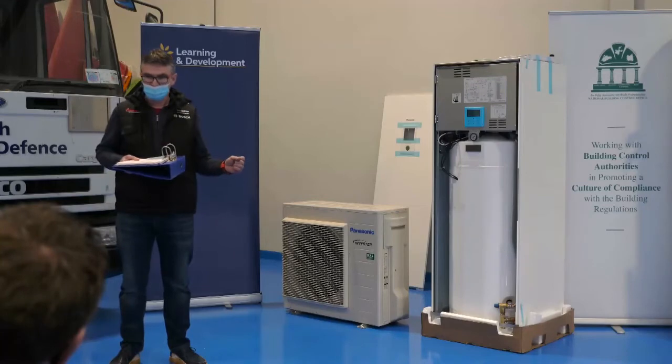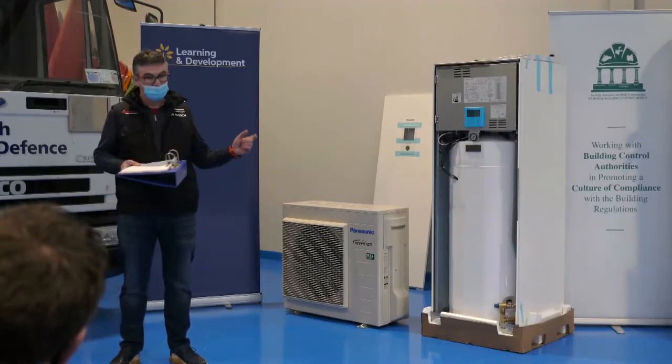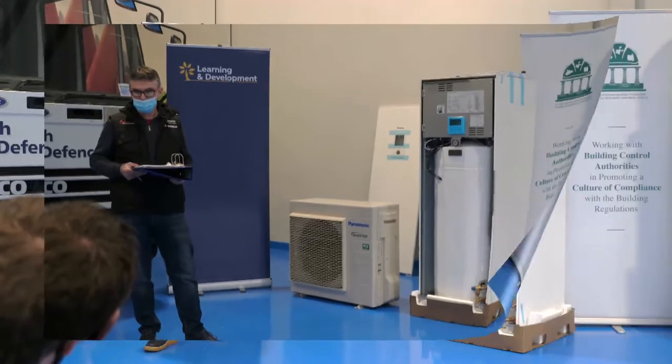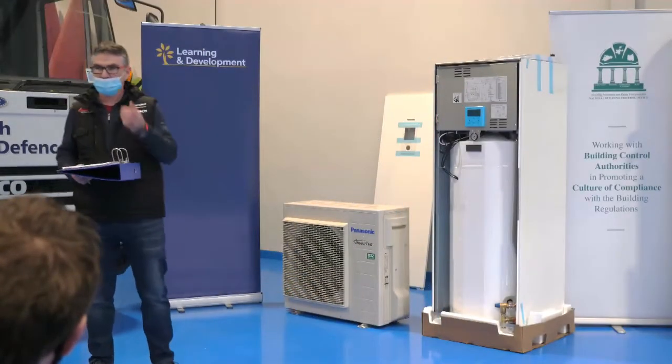The pre-charge will cover up to 10 metres of pipework usually. After that is where the F-gas engineer really comes into play. He has to weigh the gas and add gas for the extra length of pipe. Yes, a plumbing contractor can go off and get trained up to be an F-gas installer.